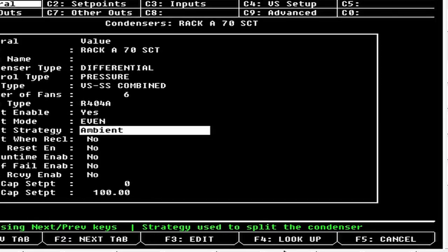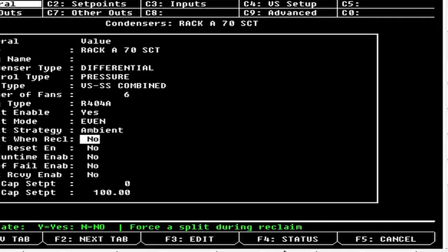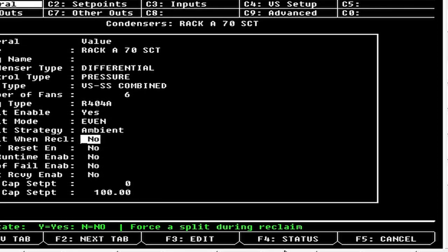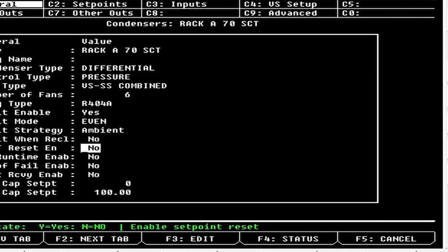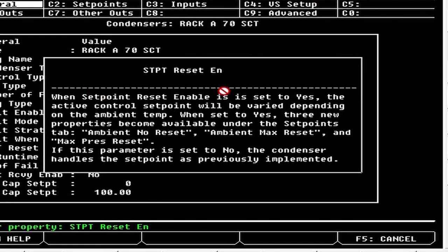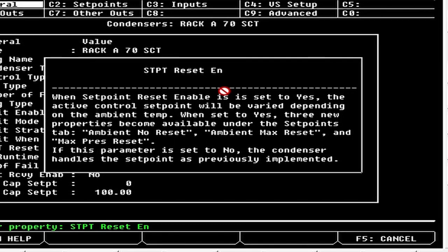Split When Reclaim is an option you don't use too often — if you have a huge heat reclaim taking up a lot of load, you may need to split within reclaim so you're not logging as much gas in the condenser. Set Point Reset Enable: when set to Yes, the active control set point varies depending on ambient temp, and three new properties appear under the Set Points tab — Ambient No Reset, Ambient Max Reset, and Ambient Max Pressure Reset. Not one I use a whole lot.